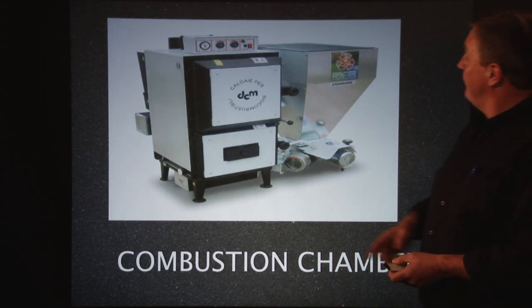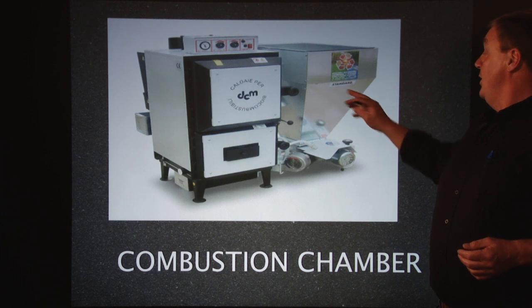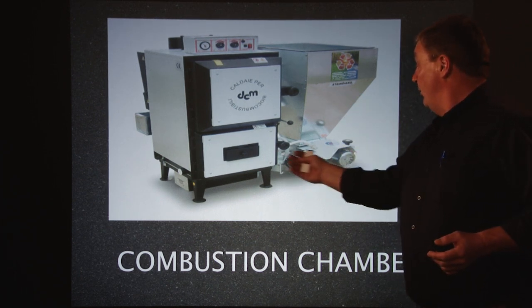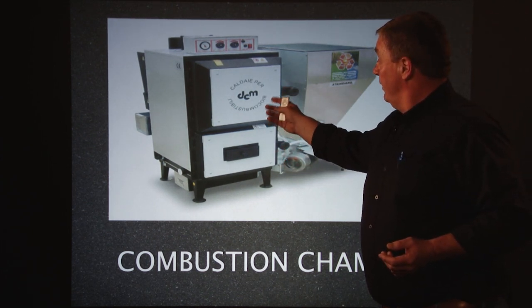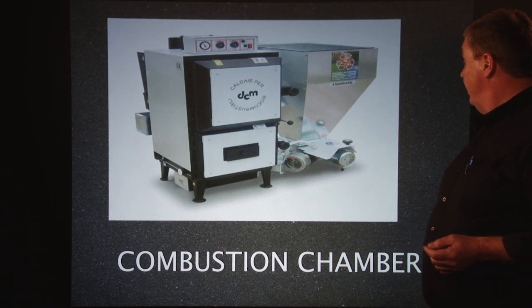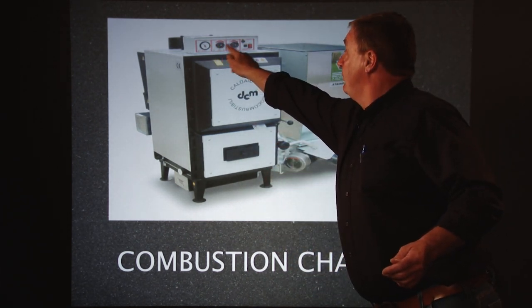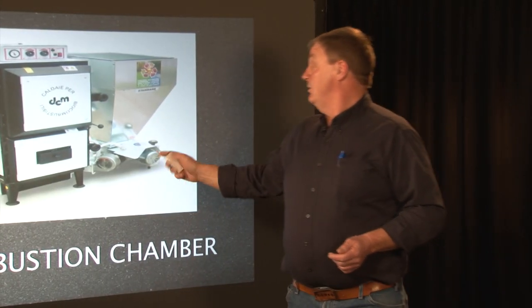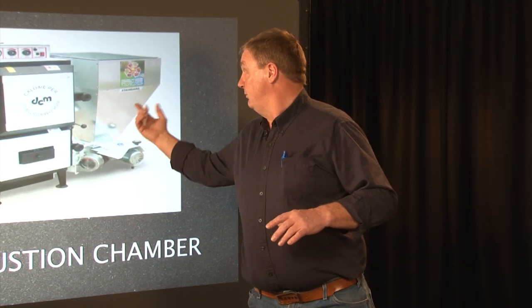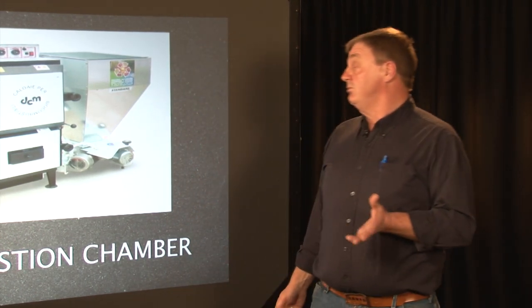You have a combustion air chamber and a solid fuel chamber. This one has an ash can that comes out and the debris gets taken away. Fans and pumps force air through. Whatever the combustible material — in this case biocombustible, so biowaste — it's burnt and the heat is transferred. This is probably a furnace, so it heats air, and then your waste is taken away. You have your control valves, control circuits, temperature and pressure gauges. There's a hopper that feeds the biowaste in. Your inspector will tell you whether the pumps and motors are working well and give you a report on BTU rating, efficiency rating, and how old it is.